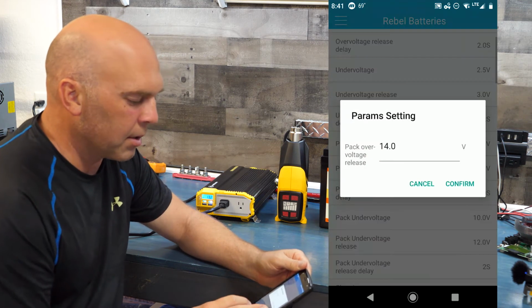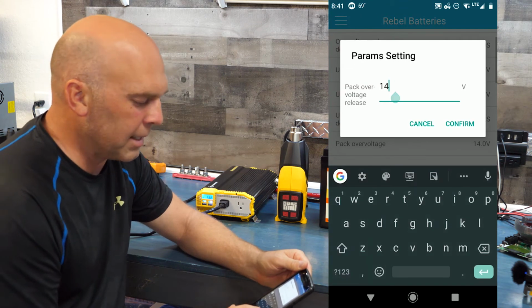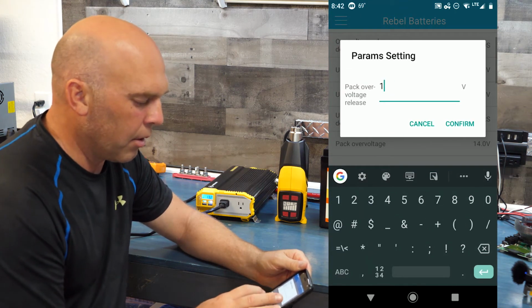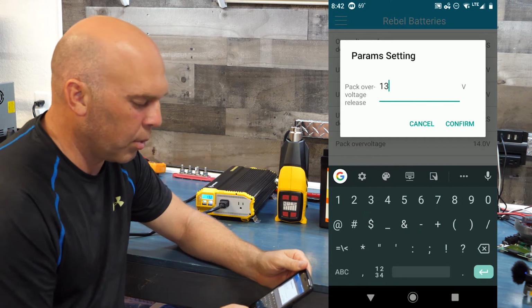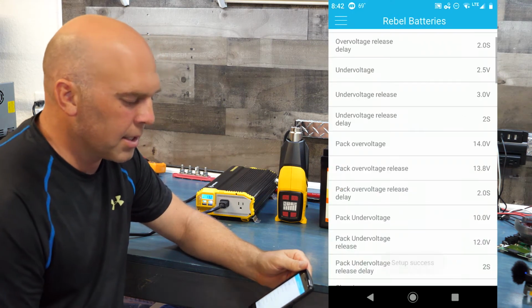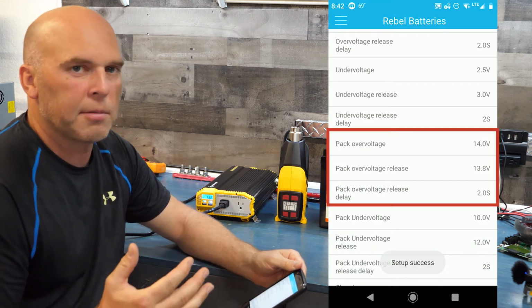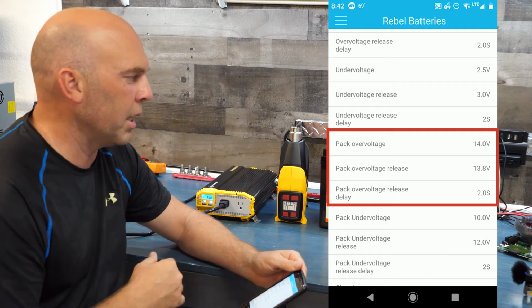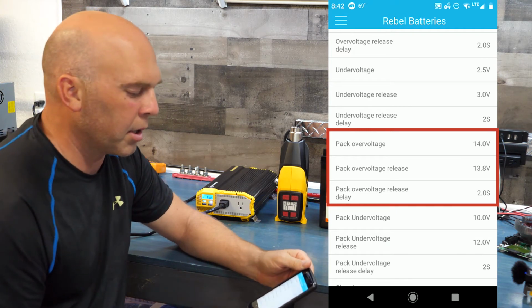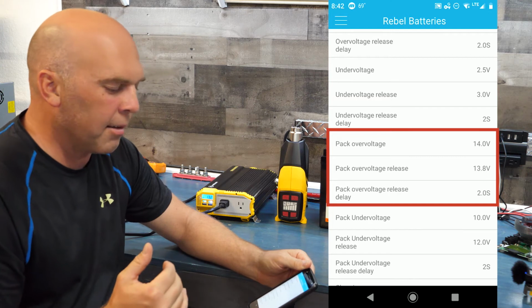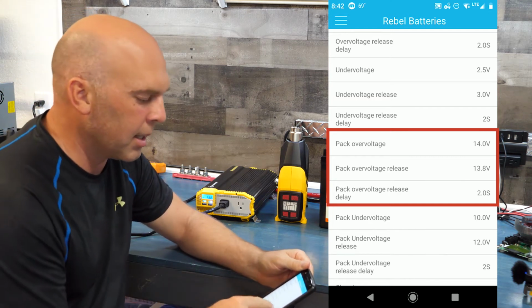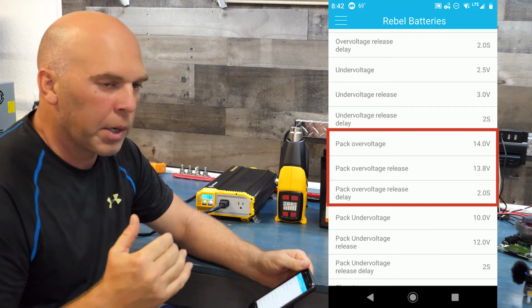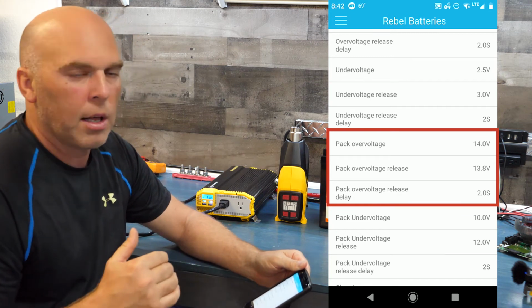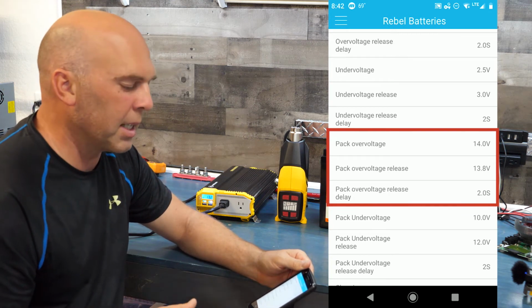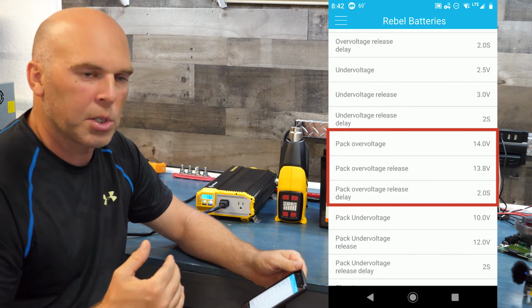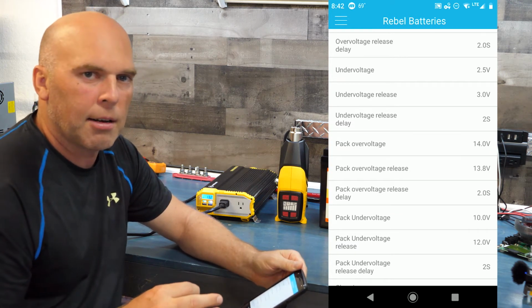Then we would also have to change the over voltage release, which we could change to 13.8. So now when the pack hits 14 volts, it's going to turn itself off for charging. It's not going to allow any more charging until it gets to 13.8 volts for at least the delay time, 2 seconds. So it has to drop below 13.8 volts for at least 2 seconds, and then it will allow itself to be charged again.